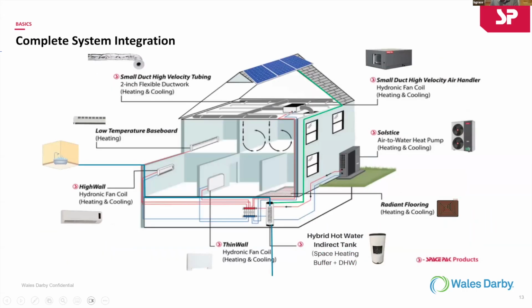Okay. So this is a summary of what you can do in the house. You have your unit on the outside of the house, and the unit is piped hot, and the two water pipes go from the unit into what we call a buffer tank. The buffer tank is in the house, and it becomes the source of heat. It's a storage of the hot water or the cold water, depending on the time of year. And then, off of that, we're piped to all the different types of emitters throughout the house.